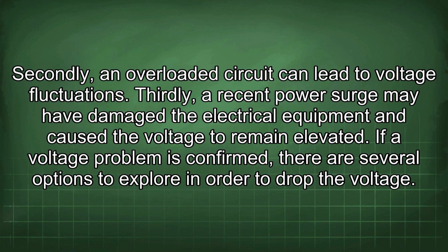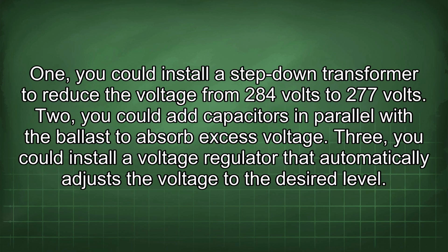If a voltage problem is confirmed, there are several options to explore in order to drop the voltage. 1. You could install a step-down transformer to reduce the voltage from 284 volts to 277 volts. 2. You could add capacitors in parallel with the ballast to absorb excess voltage. 3. You could install a voltage regulator that automatically adjusts the voltage to the desired level.